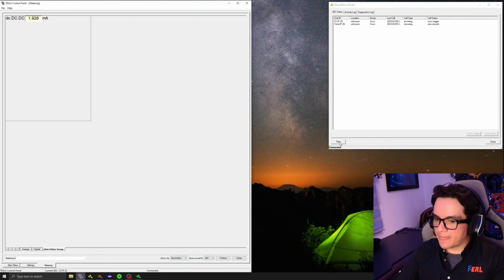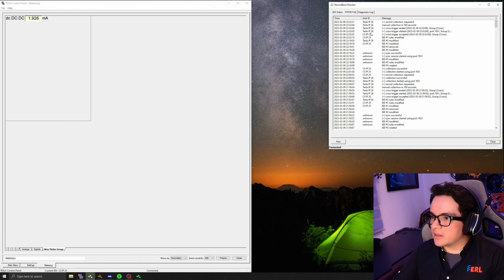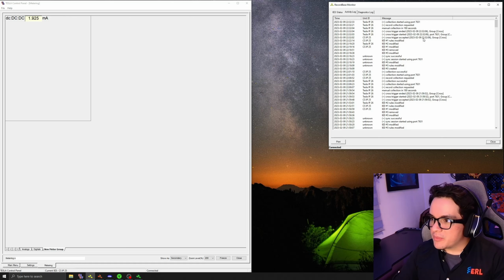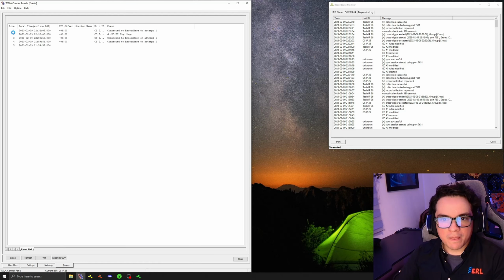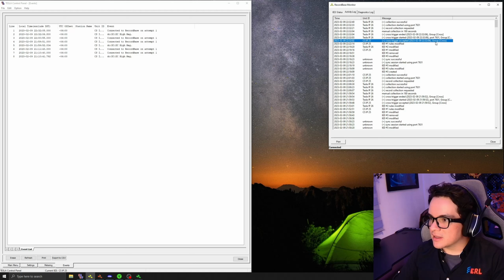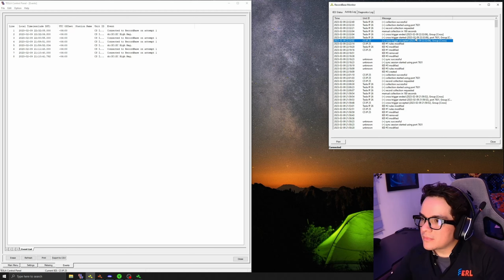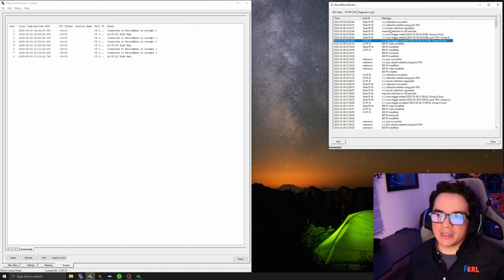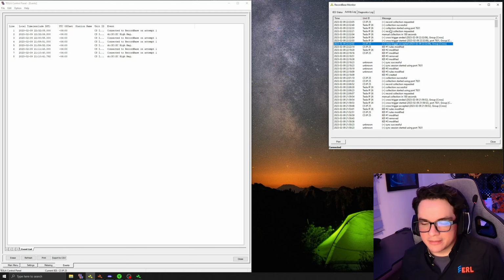Okay, that's good. I'm going to minimize this. Let's go into the activity log. Why do we have cross-trigger accepted from the record that we just created at 22:32 minutes? Let's go into the event screen. 22:32:06 and 800 milliseconds, and here it is, up to the seconds. All right, it's doing the recollection. Now it has already collected the record from Tesla IP26. Now it's going to collect the one from IP25. That was the first one to be created.